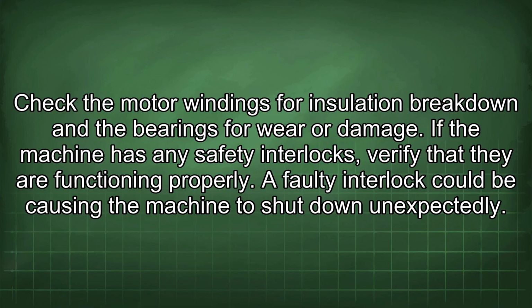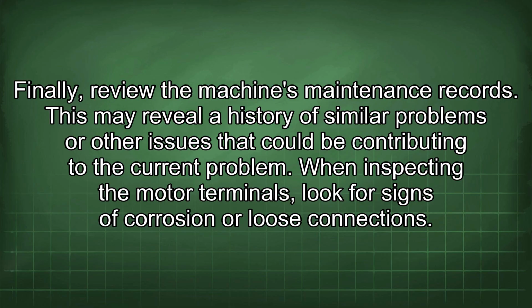If the machine has any safety interlocks, verify that they are functioning properly. A faulty interlock could be causing the machine to shut down unexpectedly. Finally, review the machine's maintenance records. This may reveal a history of similar problems or other issues that could be contributing to the current problem.